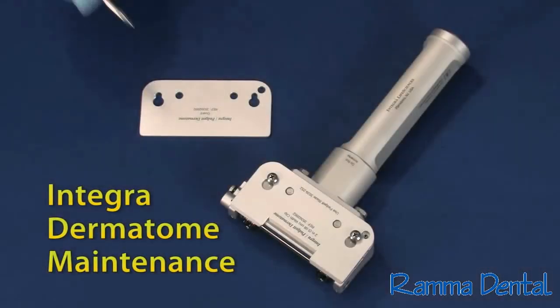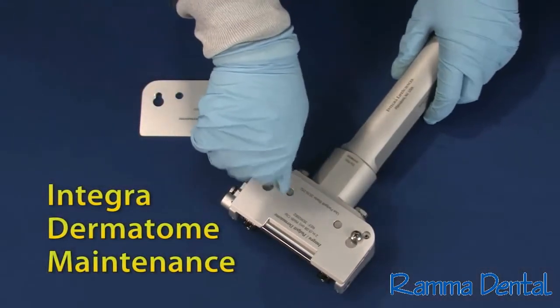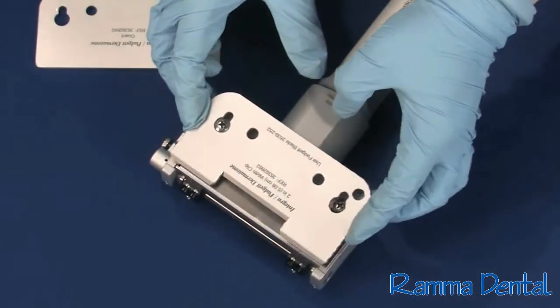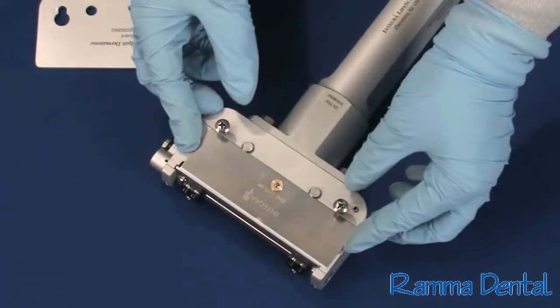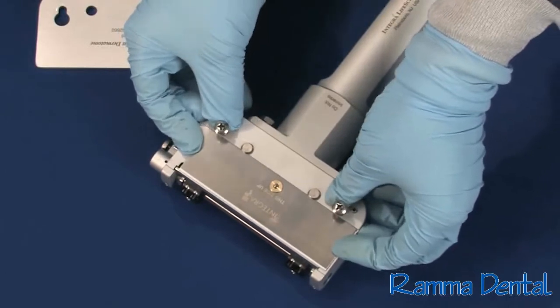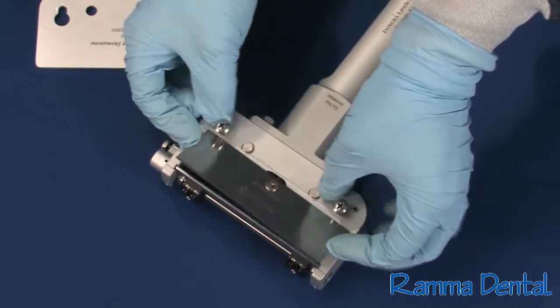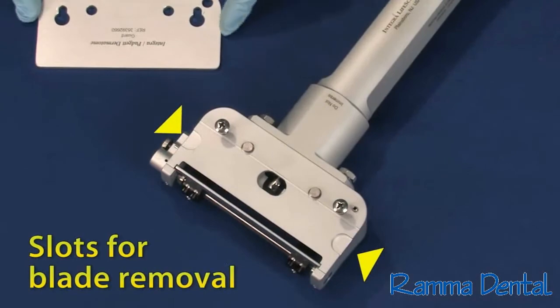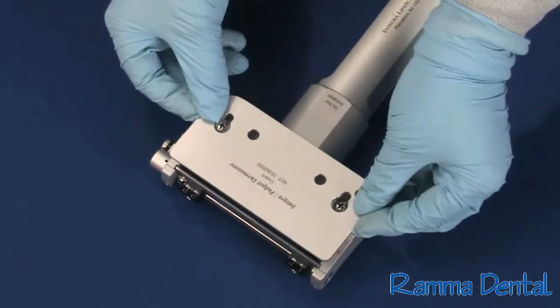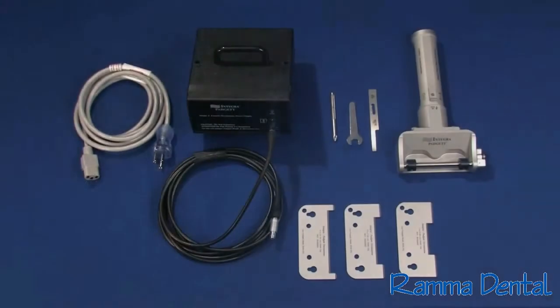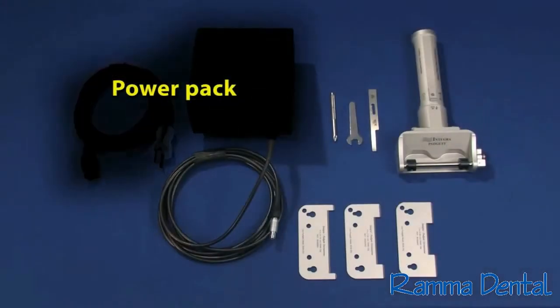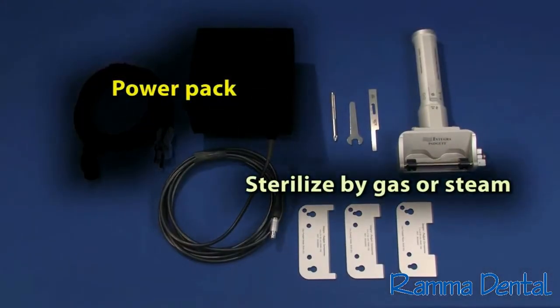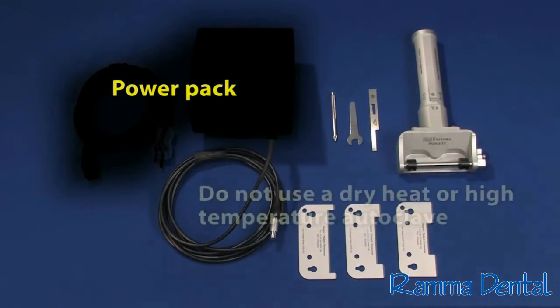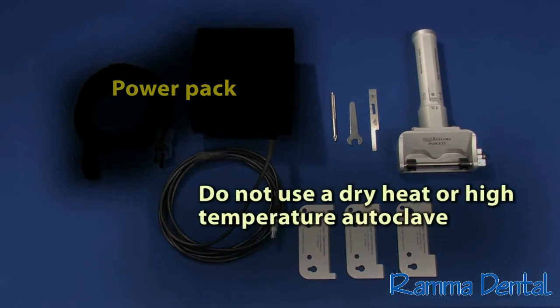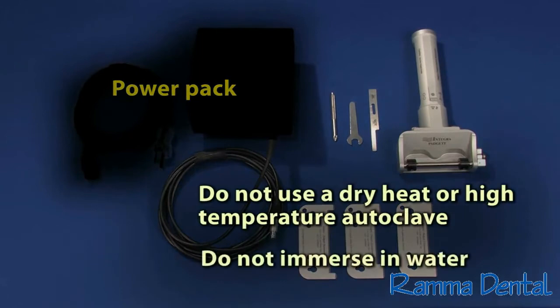To disassemble the dermatome, simply unscrew the width clip with the screwdriver and lift it off. Then remove the blade by lifting up with both index fingers, using the slots at the end of the blade. Finally, replace the guard plate. The entire instrument, cord, and plug can be autoclaved, but do not autoclave the power pack. The dermatome may be sterilized by gas or steam. Please refer to the owner's manual for sterilization specifications. Do not use a dry heat, high-temperature autoclave. Do not immerse in water.